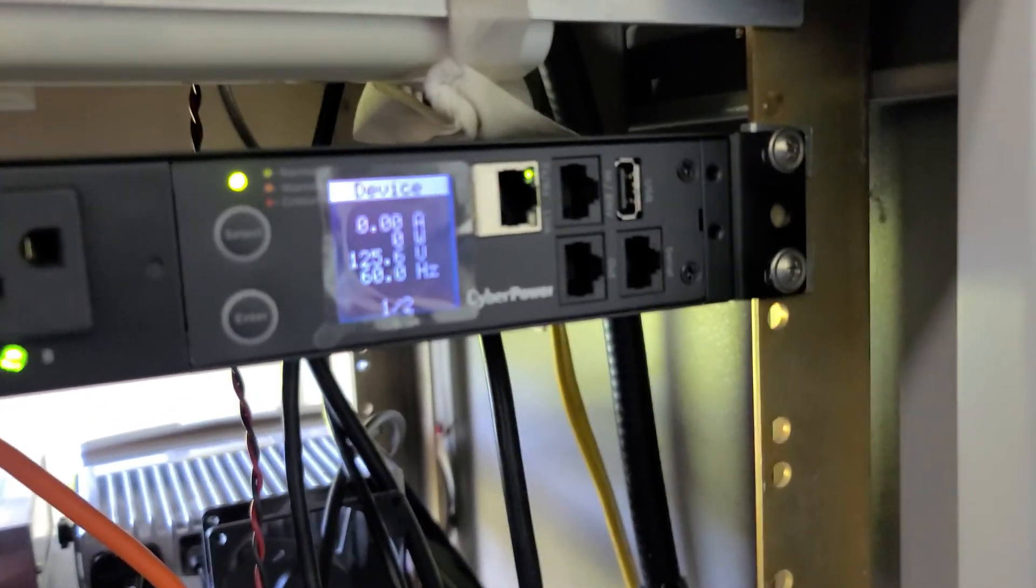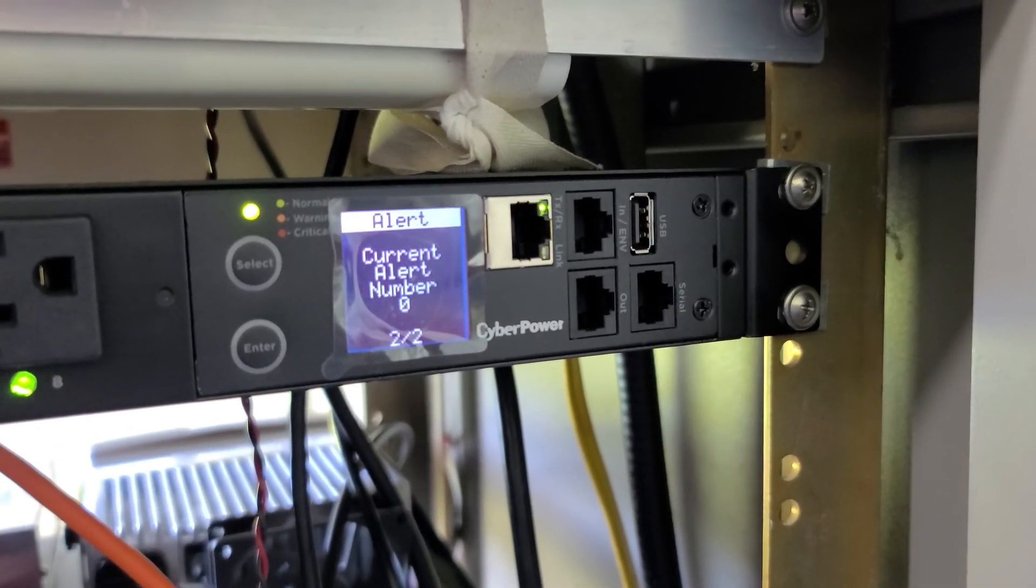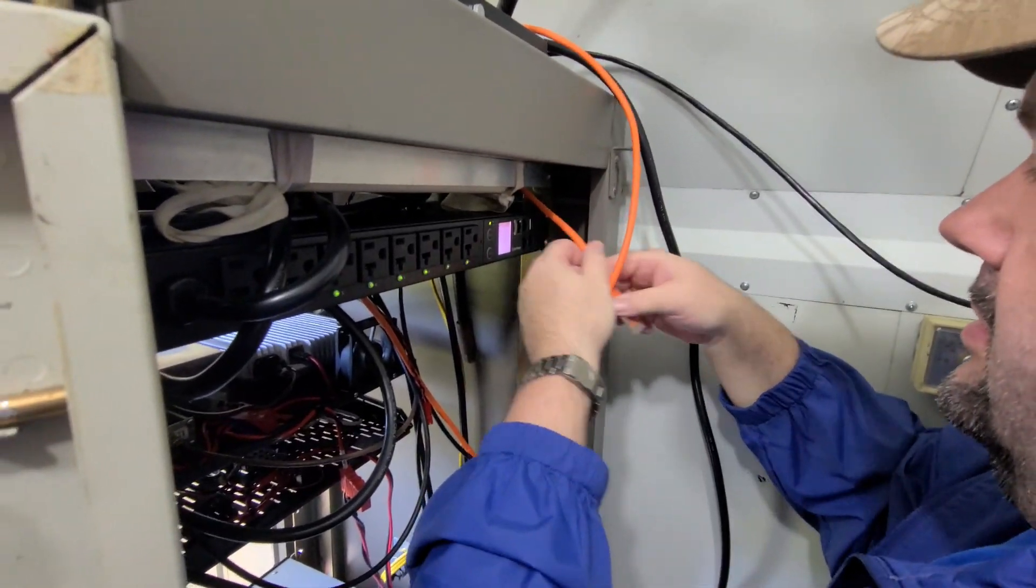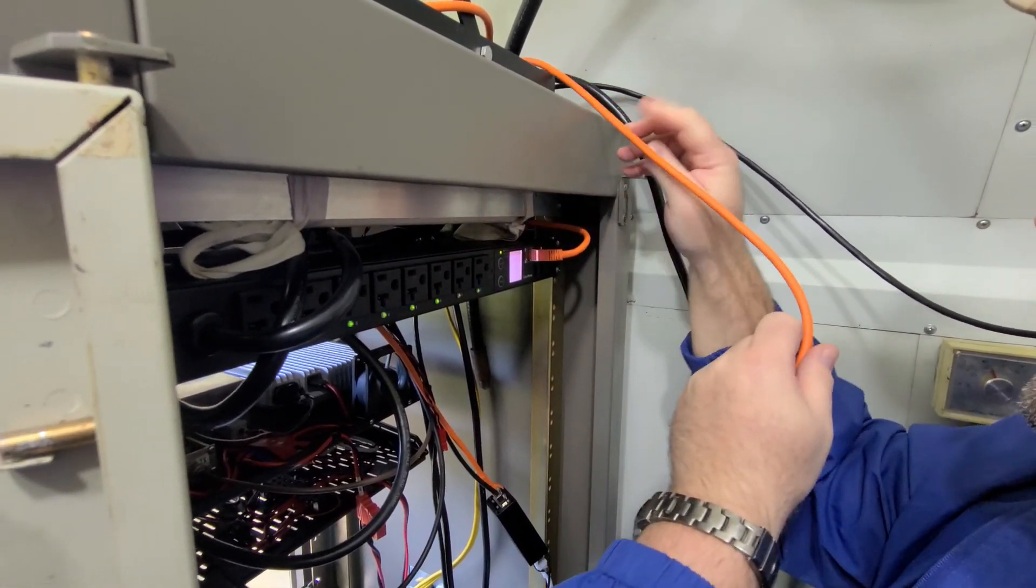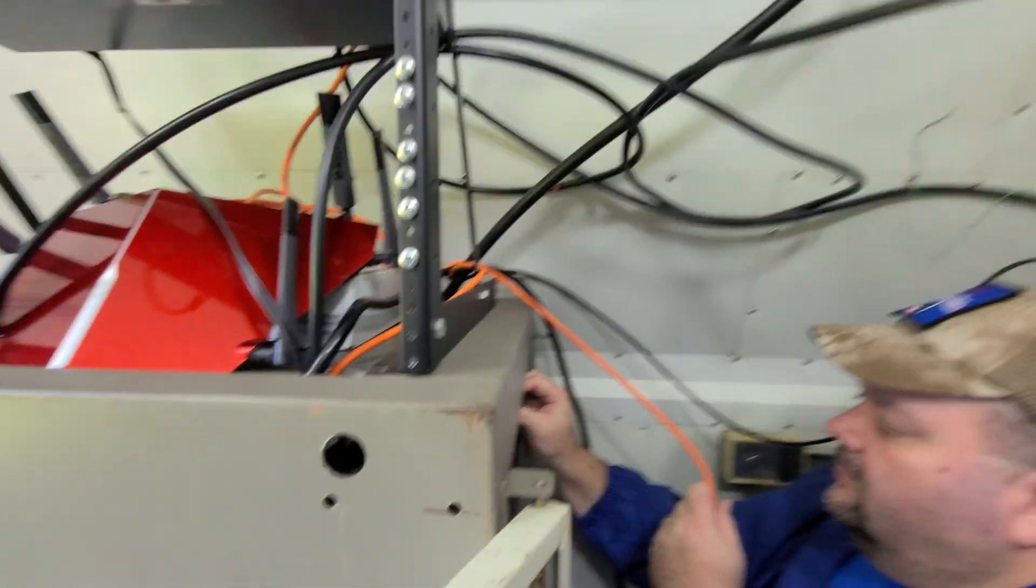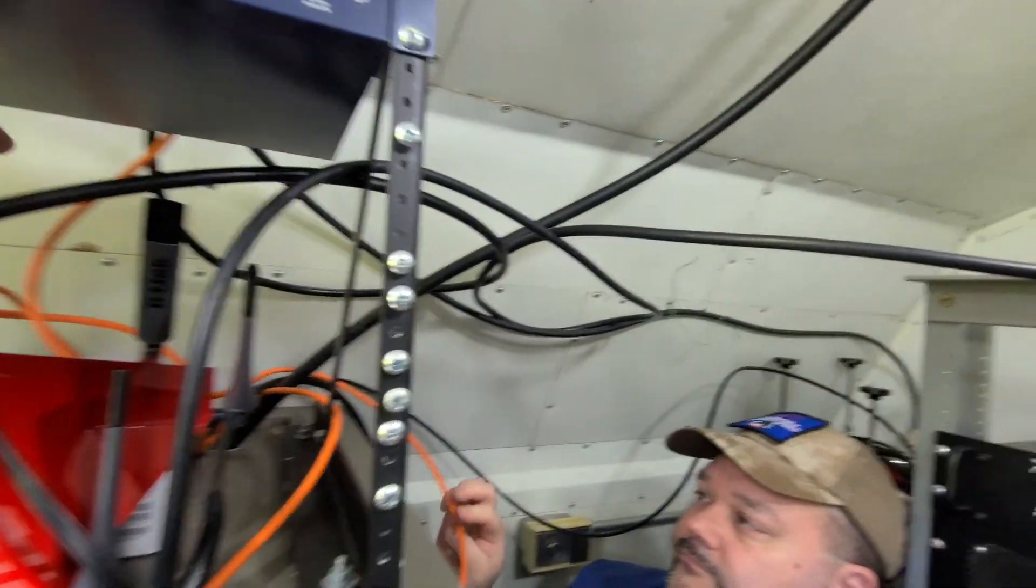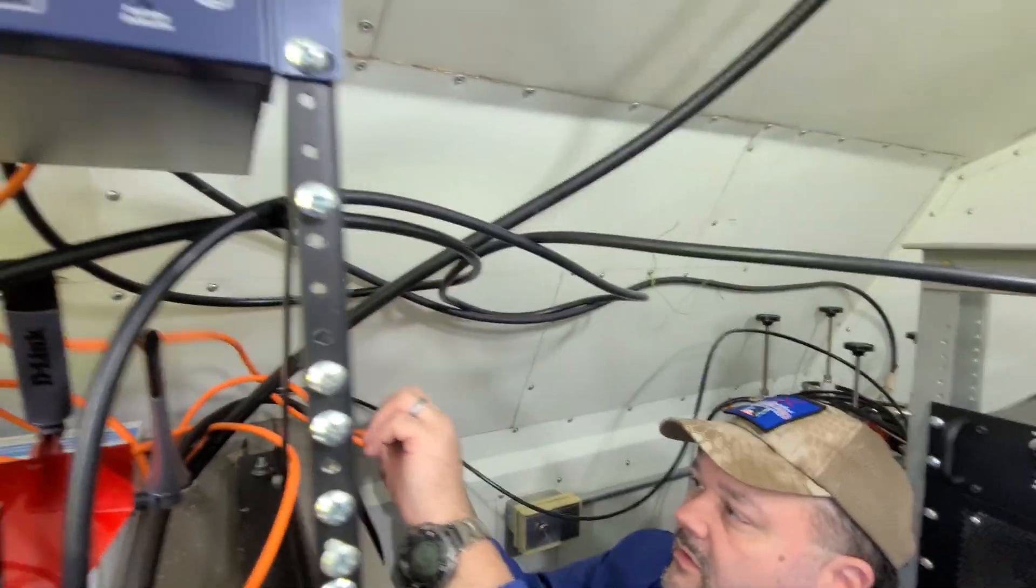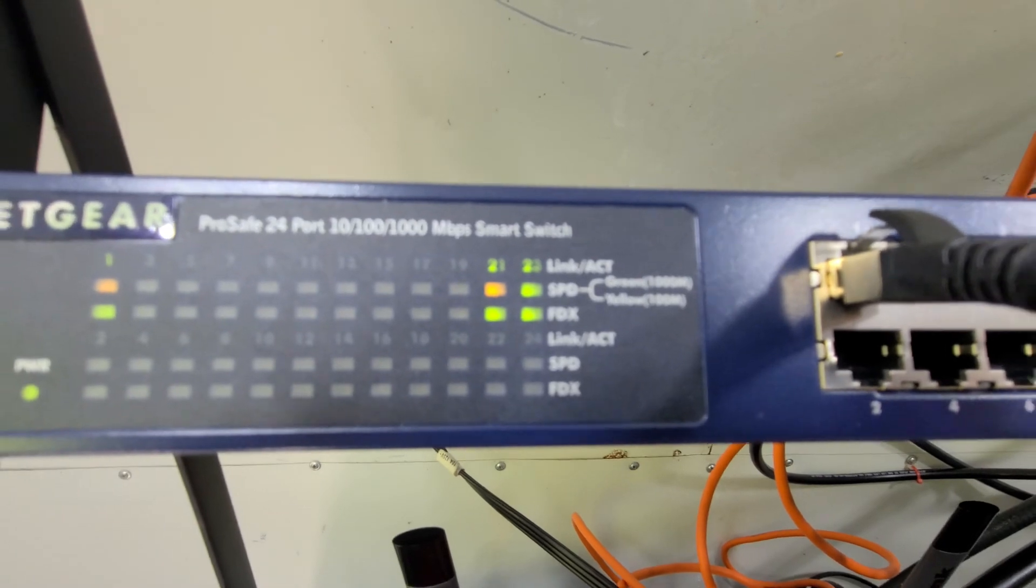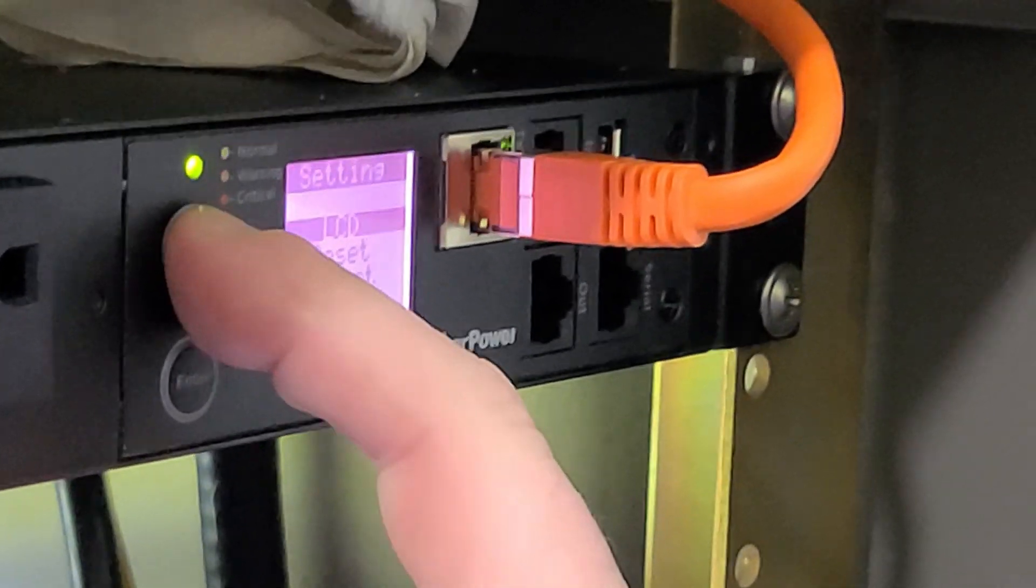Because the way the distribution unit works is each one of the power outlets can be independently managed through its web interface. And so if you have a piece of equipment that you suspect needs a reboot, you can log into this thing remotely, and you can say plug number four, reboot. Plug number seven, reboot. And you're not rebooting the entire thing. You're just rebooting that one plug.